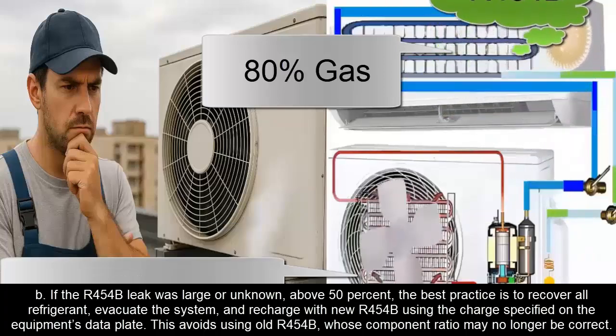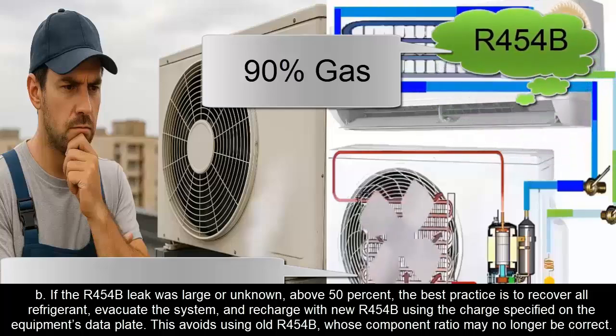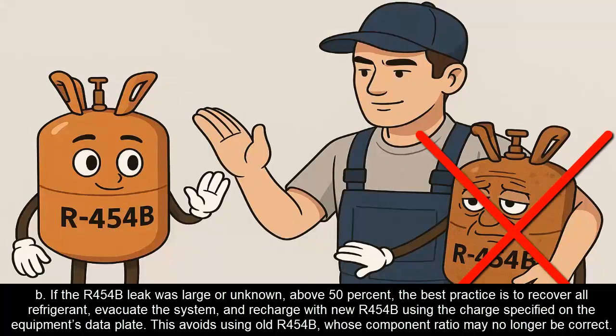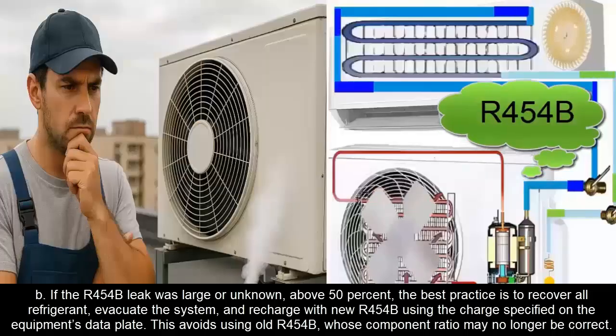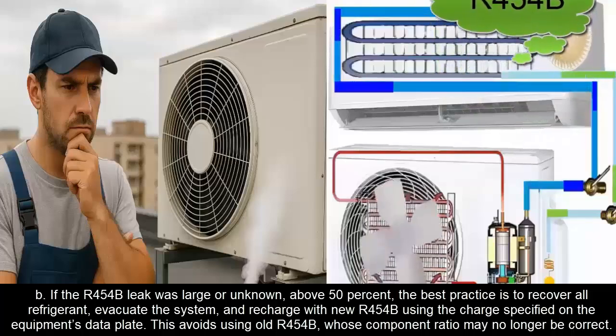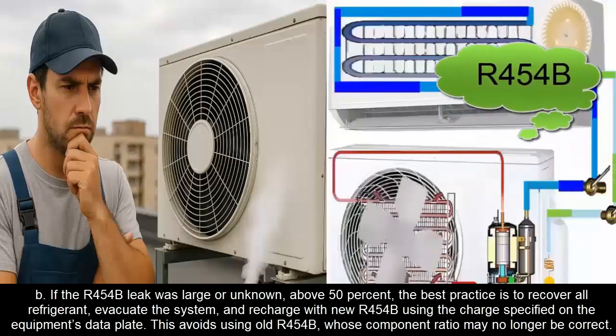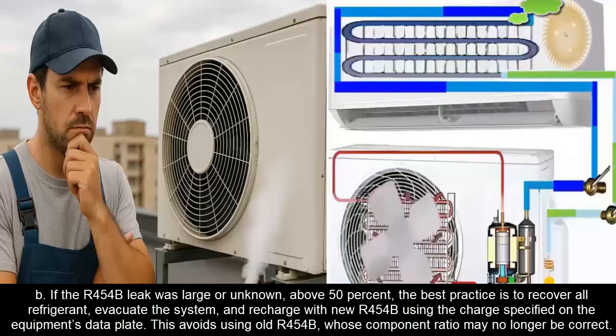B. If the R454B leak was large or unknown, above 50%, the best practice is to recover all refrigerant, evacuate the system, and recharge with new R454B using the charge specified on the equipment's data plate. This avoids using old R454B, whose component ratio may no longer be correct.